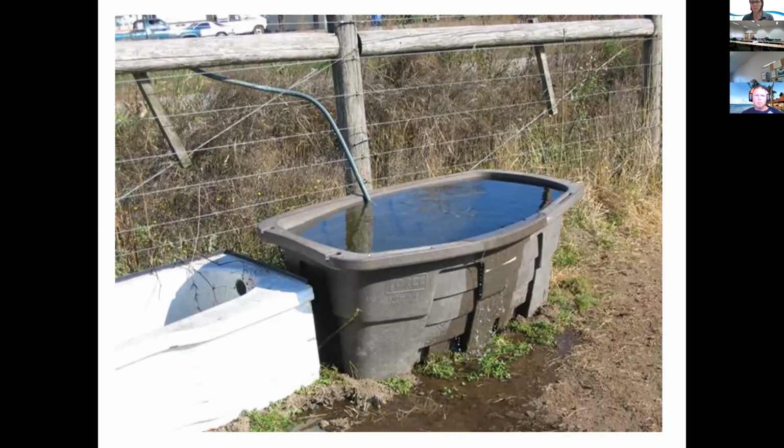Again, watering troughs. I went out and I was doing a hazard survey at a farm, and it was an almost identical situation, where they left the water cracked because they didn't want this to freeze. So they had constant water running so that it wouldn't freeze, which is scary, right? Because if you lost pressure, you have an opening directly to your potable water supply. It's going to suck everything out of here. And I like horses, but I don't want to drink anything that's been in their mouth.